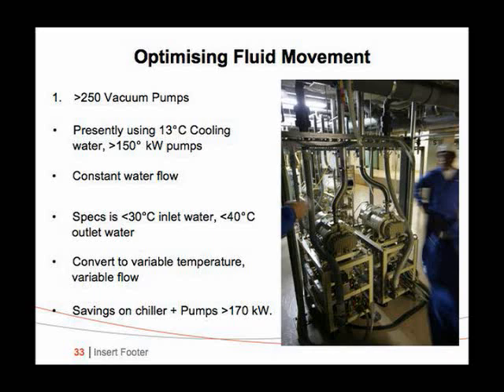They have constant chill water flow through the pump, even when it's not working, which is most of the time. So I told the Japanese fab manager, who is a very nice guy, why don't you pull out your specs in Japanese? I can't read it, but you read it and you tell me what the spec says. And I know the spec doesn't say 13. So the spec is less than 30. And you can go to the outlet being 40. And there are no other constraints.